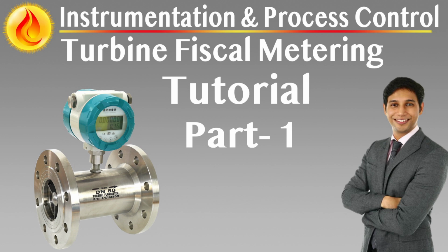Instrumentation for primary parameter acquisition. The inlet header must be equipped with a calibrated pressure transmitter and analog pressure gauge, each providing redundant verification of line pressure. Temperature measurements require both a transmitter with a thermowell and a mechanical temperature indicator, each installed in separate thermowells for cross-checking and diagnostic transparency. The physical separation of thermowells ensures independent sensing and prevents common mode failure.